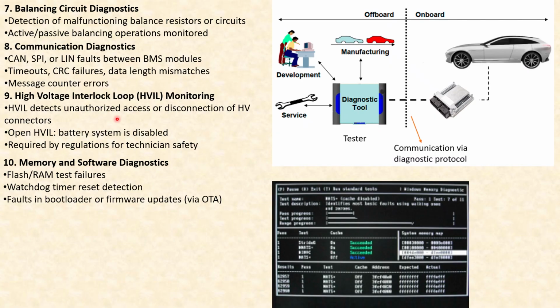Now, when it comes to high voltage interlock loop monitoring, HVIL detects unauthorized access to the HV components. When the HVIL is open, the battery system is disabled, as required by regulations for technician safety. When it comes to memory and software diagnostics, it covers flash and RAM test failures, watchdog timer reset detection, and faults in the bootloader or firmware updates via over the air.